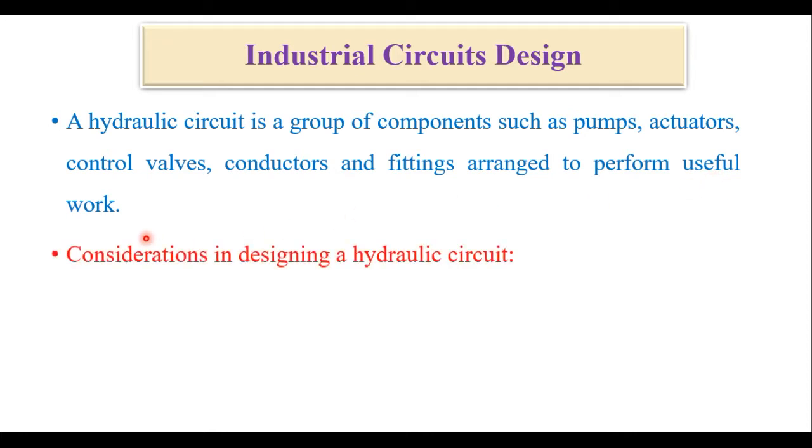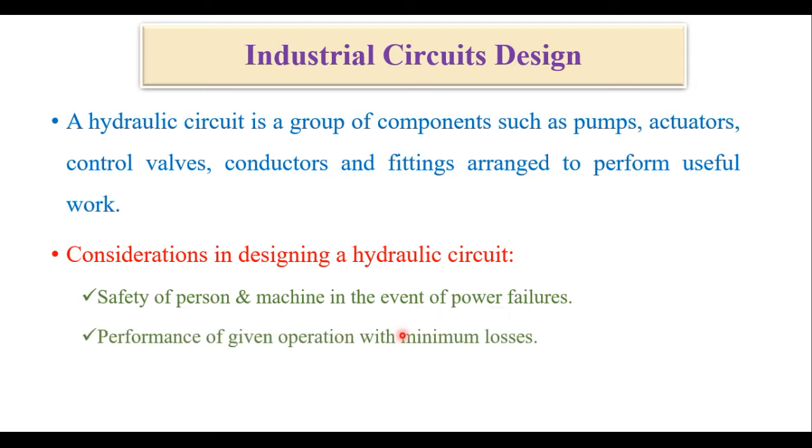What are the considerations in designing a hydraulic circuit? First and most important: safety of person and machine in the event of power failure, because hydraulics work under very high pressure range, 200 to 700 bars. Second: performance of a given operation with minimum losses.